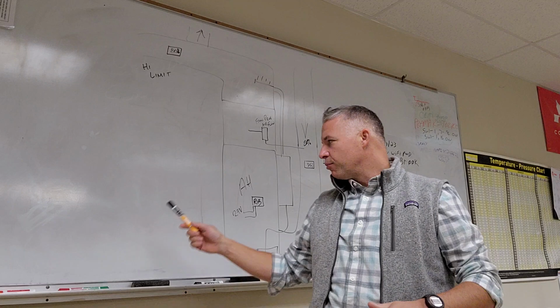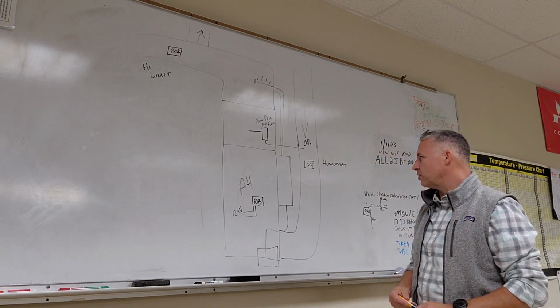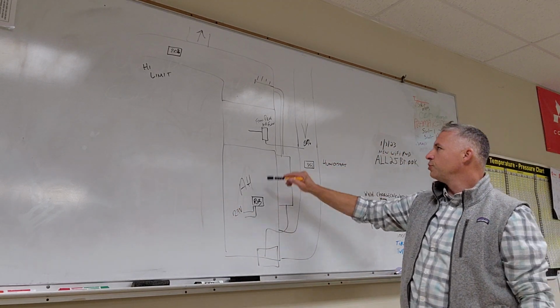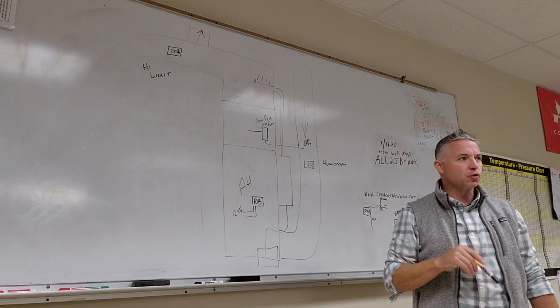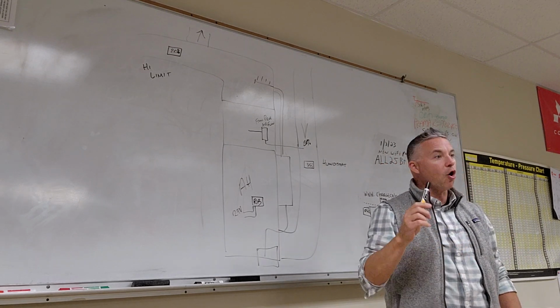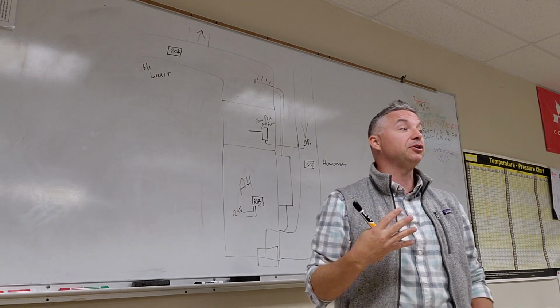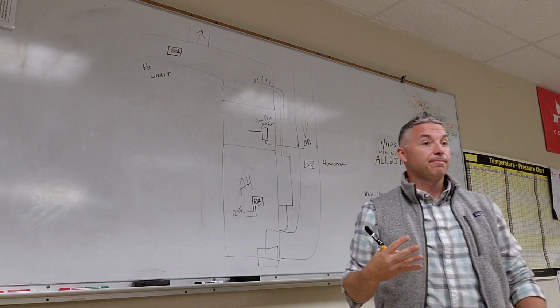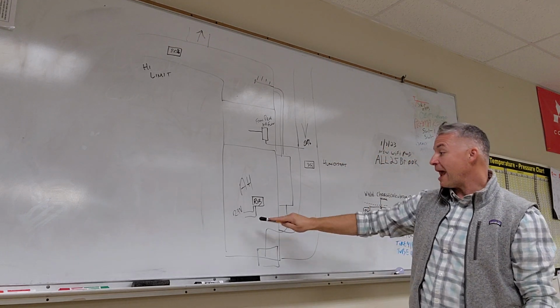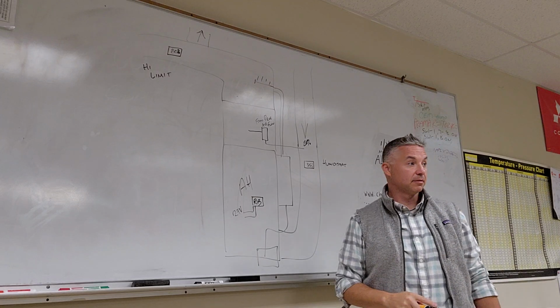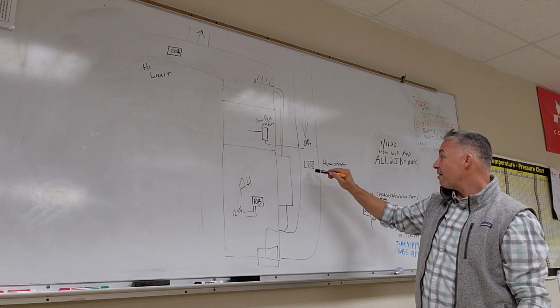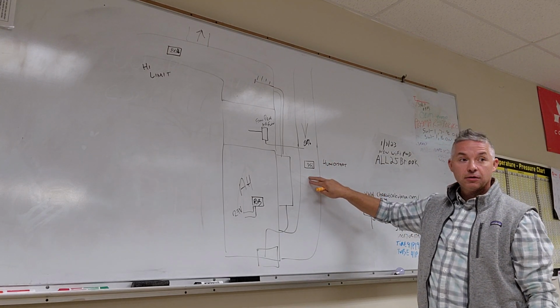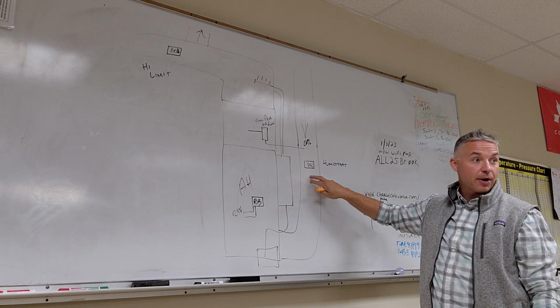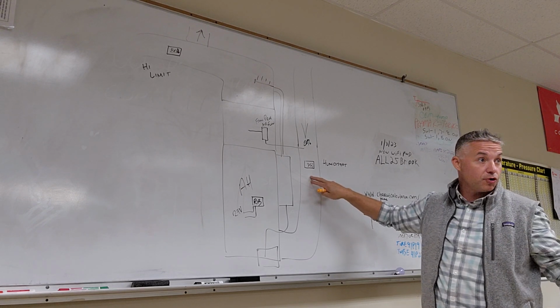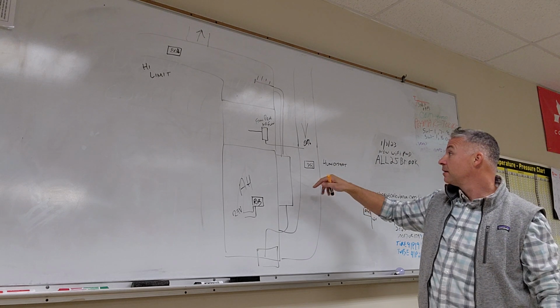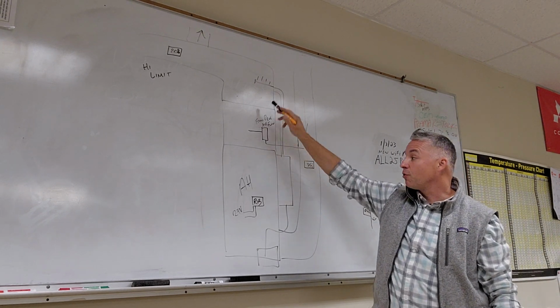So we put RIB relays in, and we said to ourselves, okay, so 1, 2, 3, 4 controls wired in series, which means all 4 of those have to prove to be true. All 4 of them. Which means we have to have a 24 volt call for fan. We have to have a call for humidity on our operating or our low limit or our humidistat, call it what you like. We have to have actual fan moving.